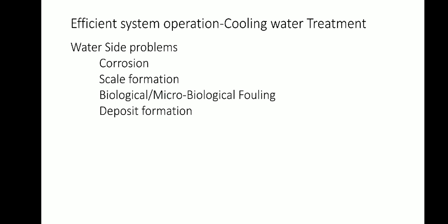Then biological or microbiological fouling. Systems exposed to sunlight often meet with the severe problem of algae formation. Other problems associated with algae are slime, moss, fungi, and various species of bacteria. Bacteria being miniature bodies of which growth is not controlled can lead to the formation of fine masses of suspended particles that lead to fouling and deposit formation.